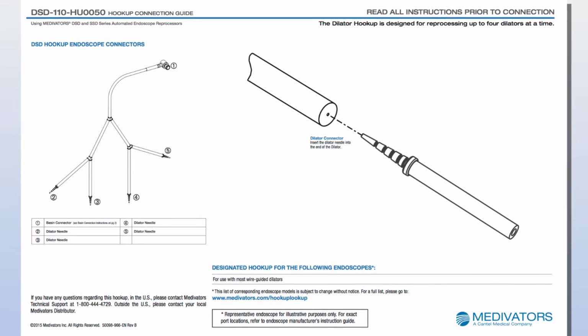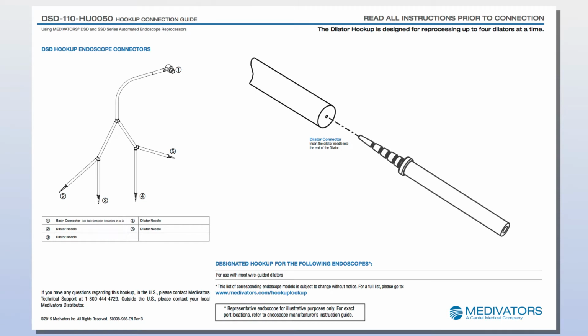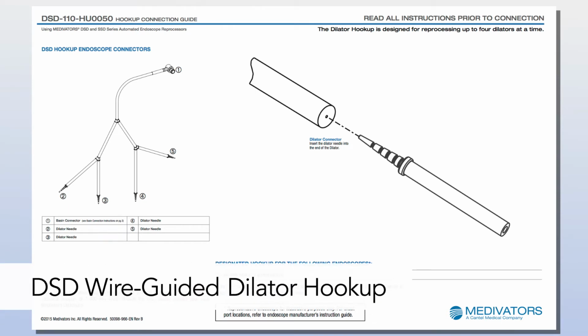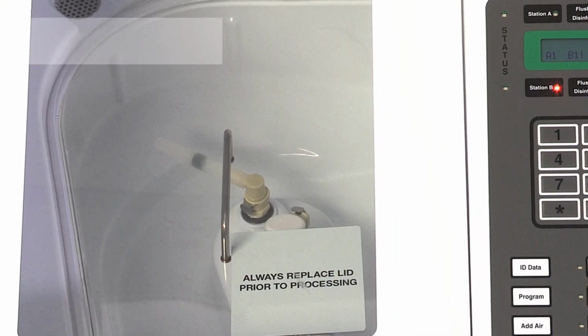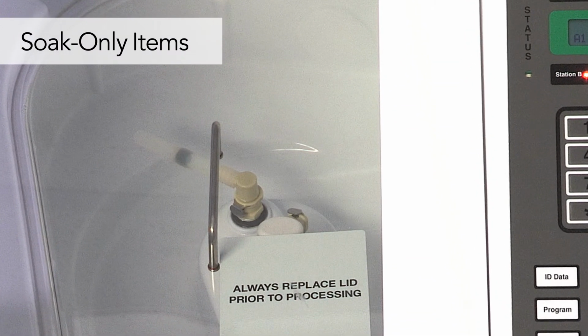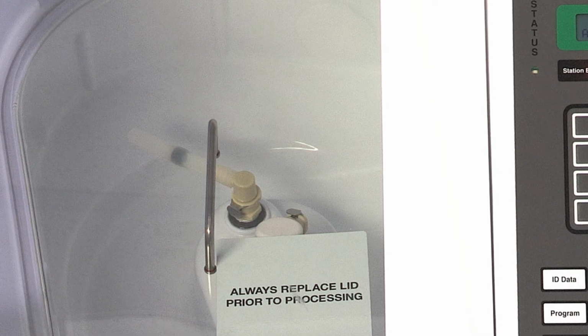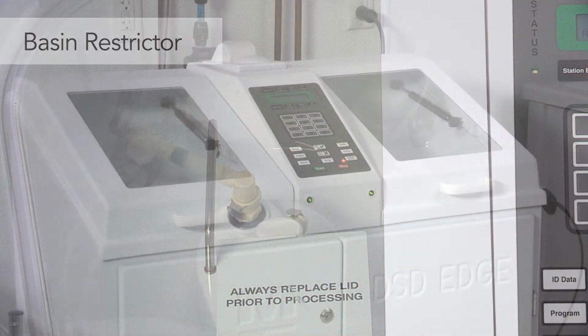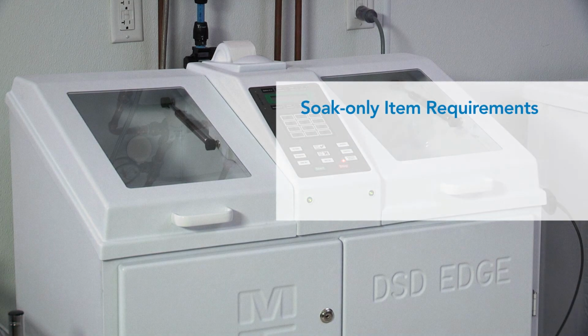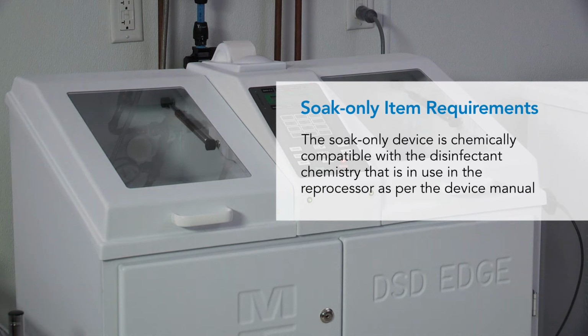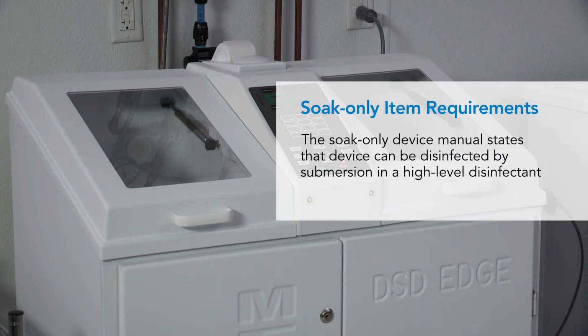Up to 4 wire-guided dilators may be reprocessed in one basin in the DSD EDGE Reprocessor using the appropriate dilator hookup. Soak-only items, for example bougie dilators that do not have a channel or require specific hookups, can be reprocessed using the basin restrictor. Soak-only devices can be reprocessed in the DSD EDGE Reprocessor as long as they meet these requirements. The soak-only device is chemically compatible with the disinfectant chemistry that is in use in the reprocessor as per the device manual. The soak-only device manual states that the device can be disinfected by submersion in a high-level disinfectant.